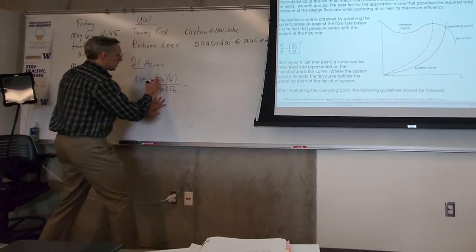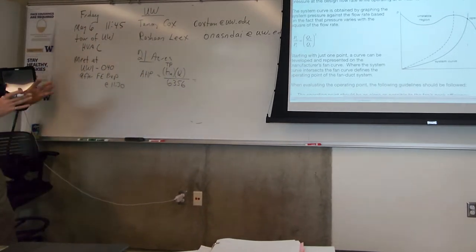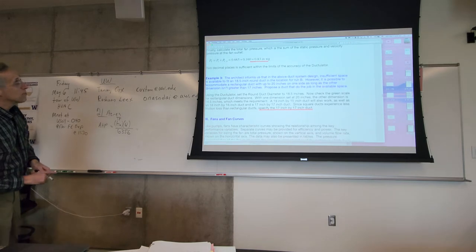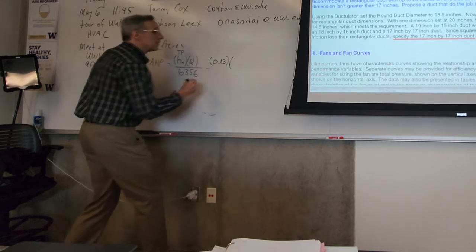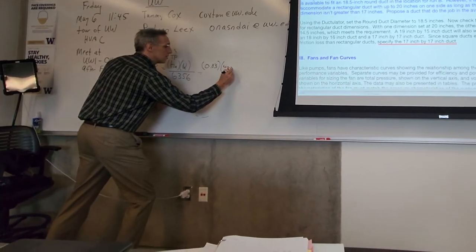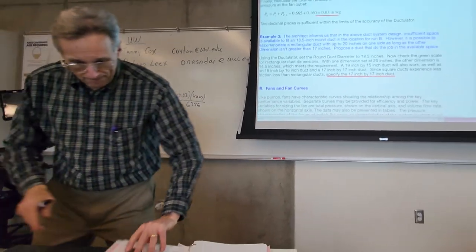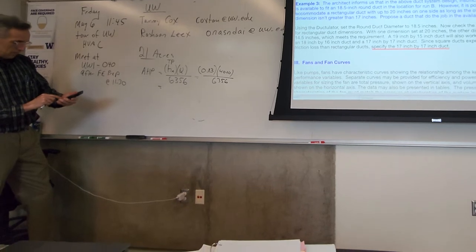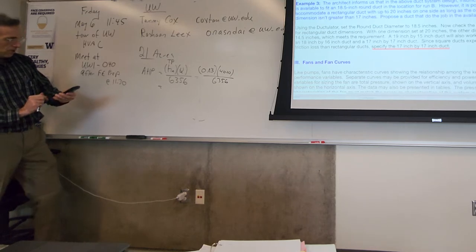6356. Okay, so our total head now, our total pressure, I think I called it in my fan equations here. It's 0.83. So I just need to make sure that's inches of water. And then my Q, it's 4,000 is my total CFM, over 6356. 0.83 times 4,000 divided by 6356 is 0.522.